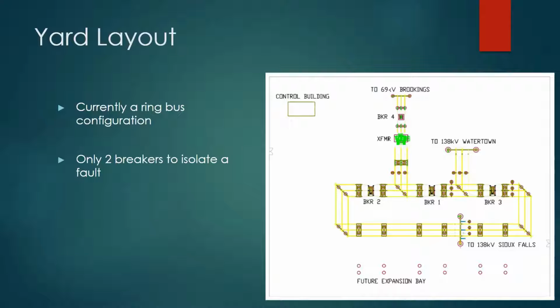Currently it's a ring bus configuration with 3 line exits. It's called a ring bus because the bus work is in the shape of a ring. It is expandable. So at the bottom of the picture, you can see a future expansion bay written. If you would install breakers down there and line exits, you could get up to 6 line exits on our substation. And that would also change the configuration from a ring bus to a breaker and a half.